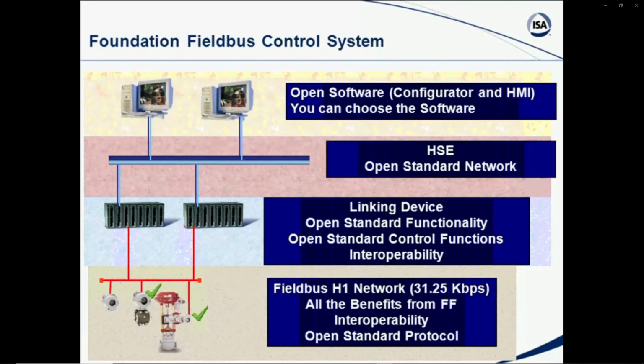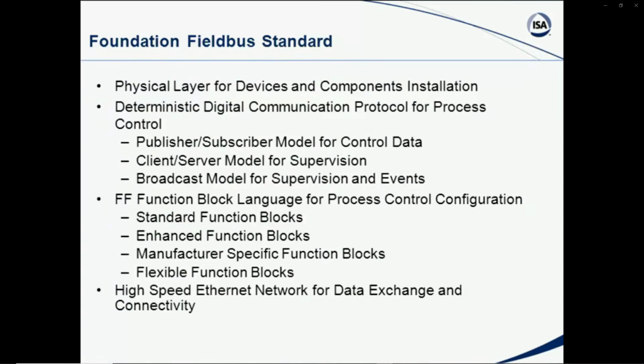But in any event, this is the basic Foundation Fieldbus control system that might get some sort of question on the exam. So the Fieldbus standard: Foundation physical layer, you have the protocol for process control, then the Foundation Fieldbus function block language to configure. Many standard function blocks, different manufacturers have specific function blocks, but you basically configure using the function block approach to that, and then using the high-speed Ethernet network, you get the data exchange and connectivity.